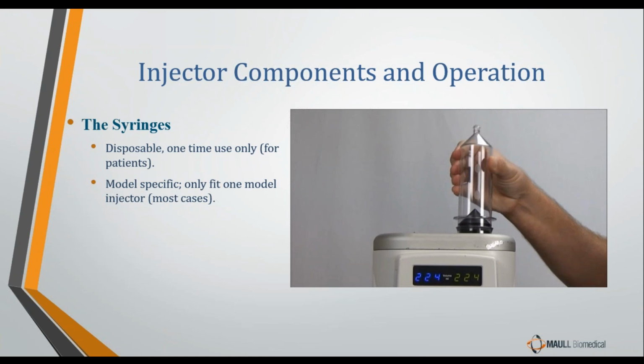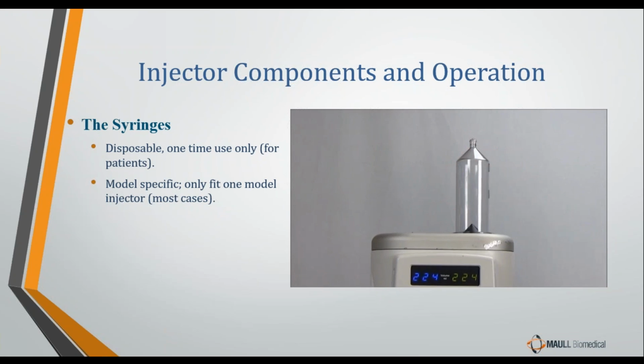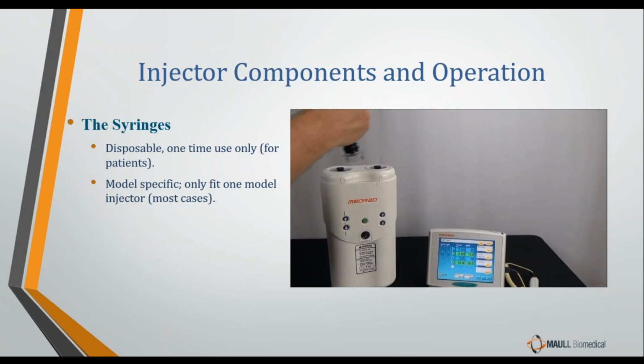But because during procedures, blood and biologicals can get on the syringe or in the syringe, they only use them one time for patient use. But again, for us, you want to keep them. They'll last you a very long time. And with very few exceptions, the syringes are model specific. When you have a syringe, you don't have a syringe for all the injectors. If you have a Stellant syringe, that means you have a syringe that just fits the Stone. It doesn't fit anything else. There's a couple exceptions to that rule. The CT9000 and the Optivantage use the same syringe. The Mark V Plus and Provis use the same syringe, but those are the rare exceptions to the rule. For most of the time, each syringe is model specific.